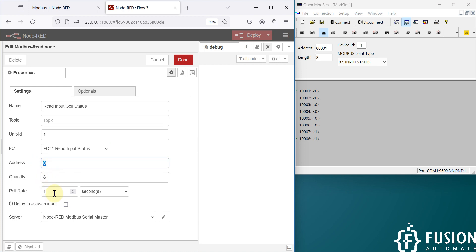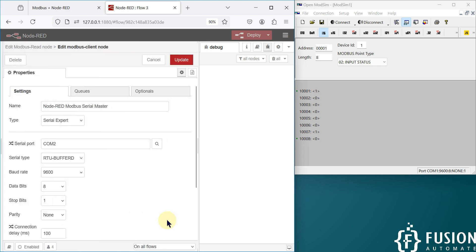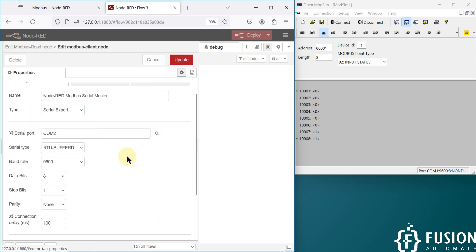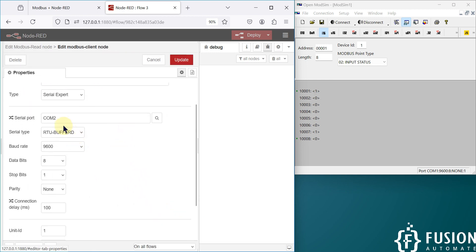The quantity we are going to read is 8, the starting address is 0, the poll rate is one second, and the server is the same one used in the last three videos: Node-RED Modbus serial master. If you click the pencil icon, you will see the configuration and connection parameters.